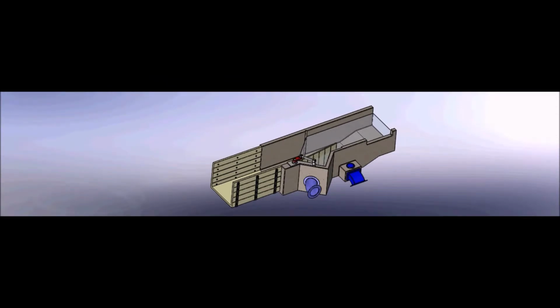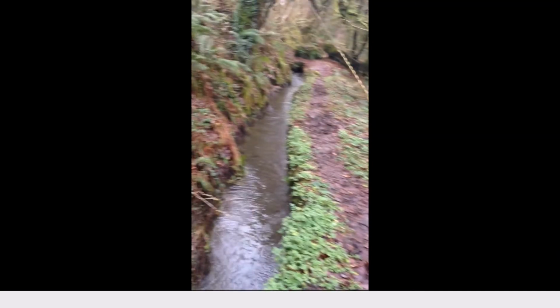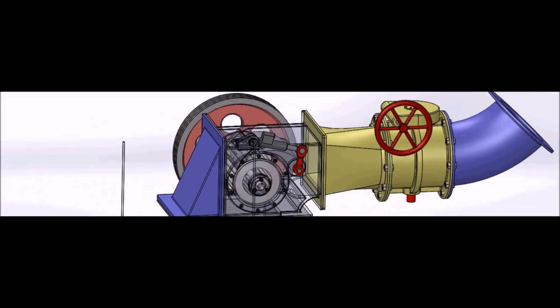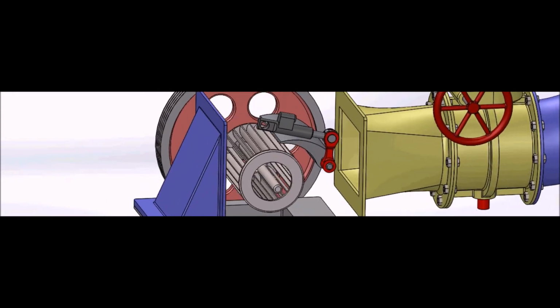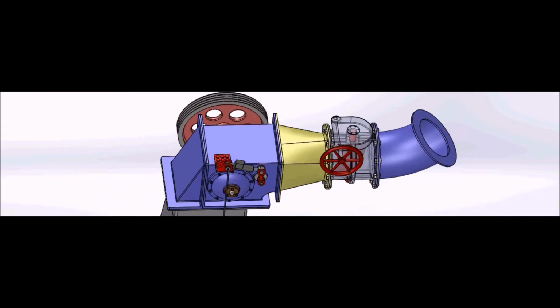This forebay tank design illustrates a potential bypass system for the fish, along with a hydraulically operated 2-way sluice gate to control the direction of water between the turbine and 18th century millhouse, incorporating the original wooden leat and flume. The site is based in Cotehele Woods, which has a high tree density amongst numerous walkways for National Trust visitors close to the turbine location. An actuator operating a runner, along with a rotating butterfly valve, demonstrates two conventional methods of regulating the kilowatt output via the control gear, here using a cross-flow turbine for demonstration purposes.